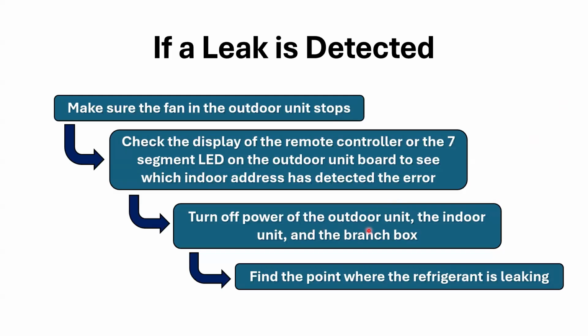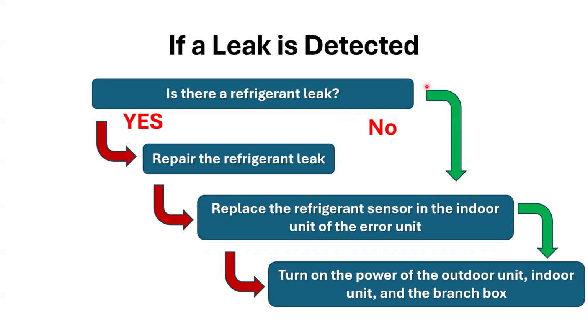Turn off the power of the outdoor unit, the indoor unit, and the branch box. Once we know, we ventilate and everything's done at this point, the unit's just sitting there. Find the point where the refrigerant leak is. If a leak is detected, is it a refrigerant leak? So this is kind of just a flow chart we made. So, is there a refrigerant leak? Yes or no? Let's say no.